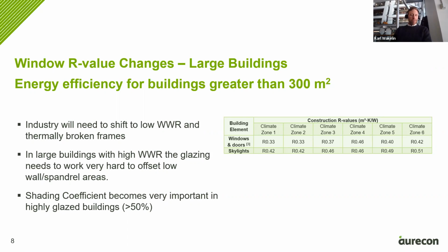What this means for large commercial buildings is that we're going to need to shift away from highly glazed office blocks or buildings. Anything above 50% window to wall ratio is going to be very difficult to achieve the requirements in terms of the reference building using more energy than the proposed building. And if you do have a highly glazed building, the shading coefficient becomes very important.